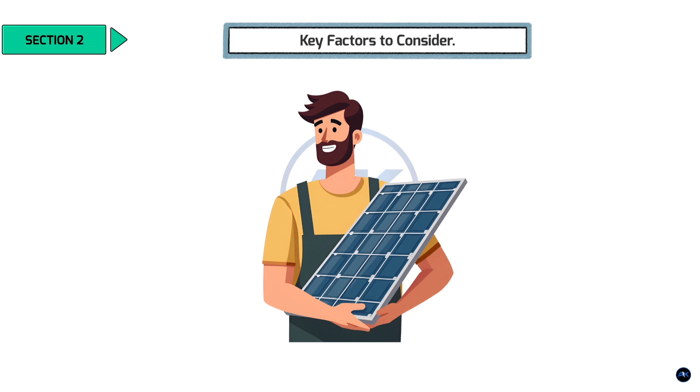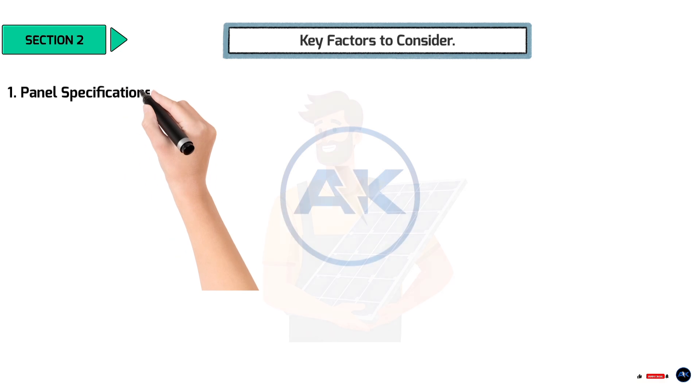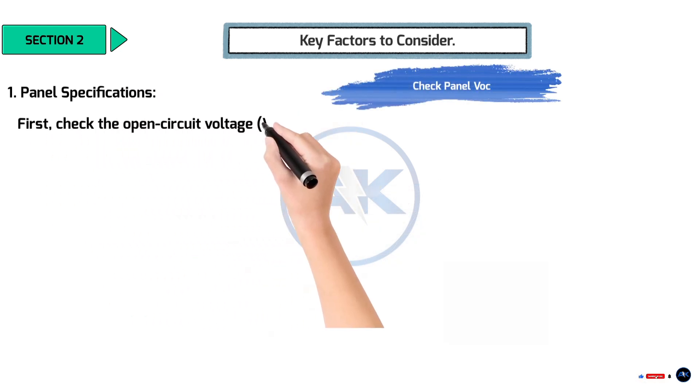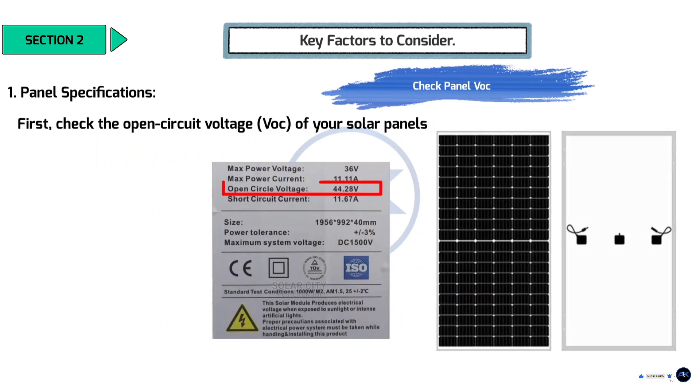Section 2. Key Factors to Consider. Now, let's talk about the key factors you need to consider when determining how many panels you can safely connect in a string. First, check the open circuit voltage, VOC of your solar panels. This is usually listed on the back of the panel or in the datasheet. VOC is the maximum voltage the panel can produce when there's no load connected.